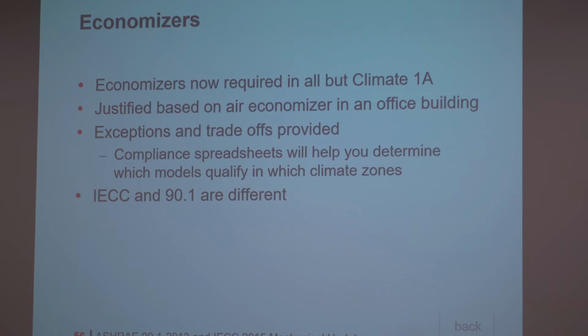There are exceptions, there are trade-offs. It is prescriptive in 90.1. I believe it is also prescriptive in IECC, so you could trade this off using energy modeling. But they are different, and I'm going to talk about how they're different. So the way that economizers are different in IECC is you have this aggregation clause. Now this is the clause that came into IECC before it came into ASHRAE, which is sort of a rare thing. It was proposed to both at the same time because the proponent was really serious about getting it in there. However, 90.1 sort of rejected it in its form that was sent to IECC and rewrote it differently and did more analysis. So there's a divergence, and I'm not sure that that divergence is ever going to close.